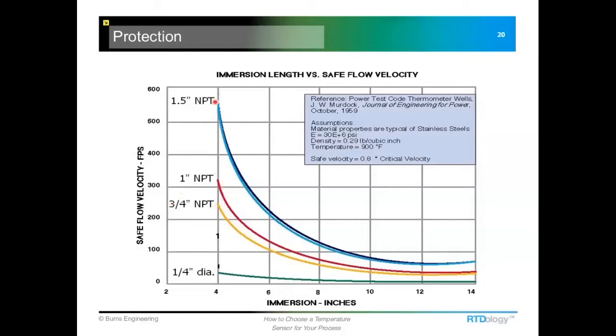So we get up here to a really larger size, and we're roughly 550 feet per second. So that's something to certainly be aware of, and I always recommend that a wake frequency and strength calculation be done on the thermowell, especially if it's a new installation, just to be sure that it's suitable for that particular process.